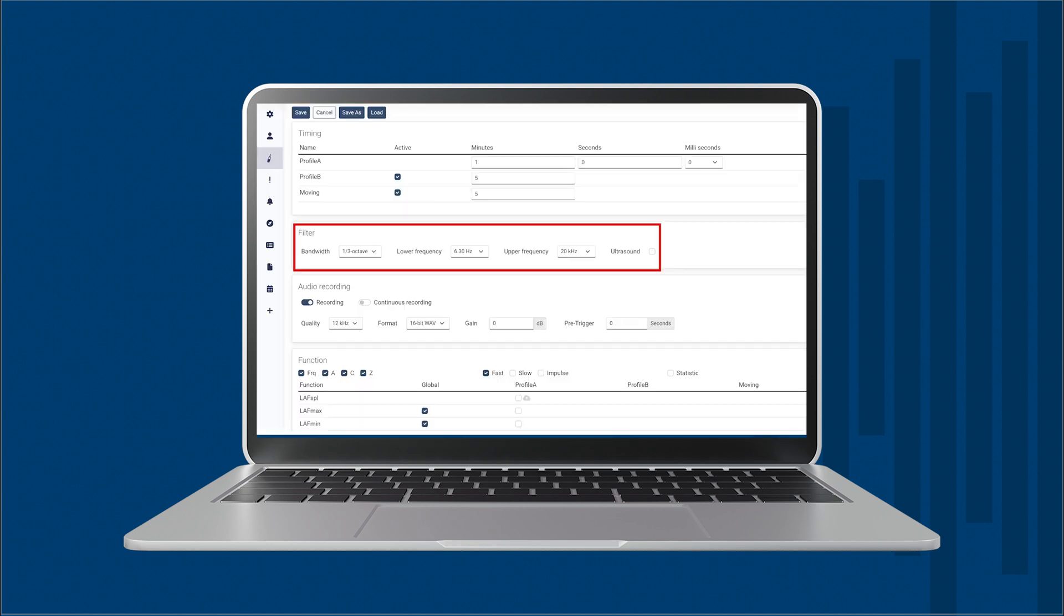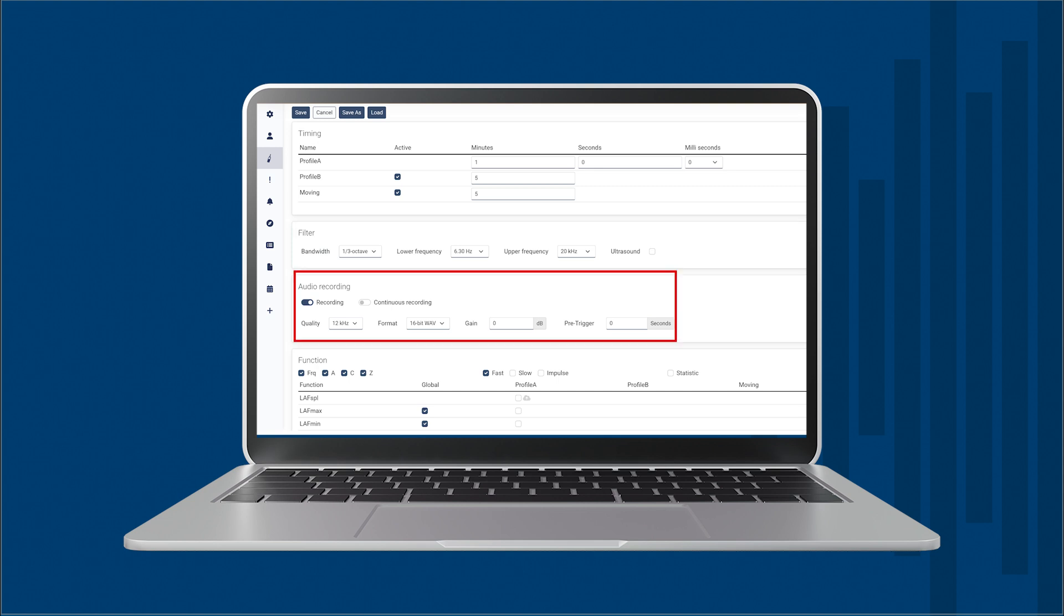In the filter section we choose between octave band or octave thirds, as well as the frequency range. We can even make measurements that include ultrasound range using the Norsonic ultrasound microphone for our NOR 145.